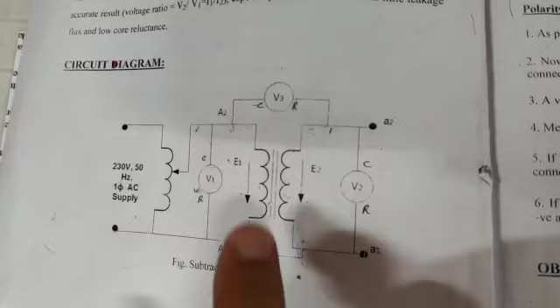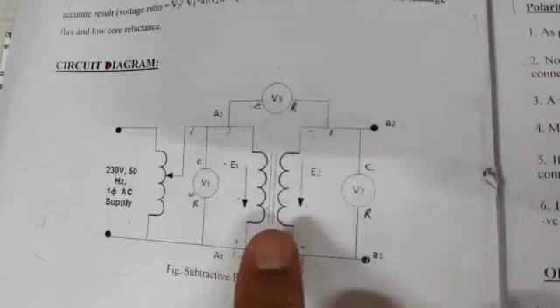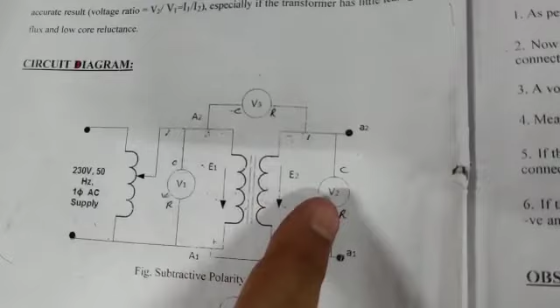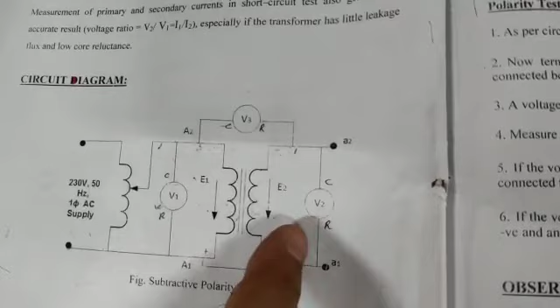Now we are going to start the third test, called the polarity test. The circuit diagram for the polarity test is: single phase transformer, auto transformer, voltmeter 1, voltmeter 2, and voltmeter 3. V1 is connected in the primary, V2 in the secondary, and V3 between the primary and secondary of the transformer.